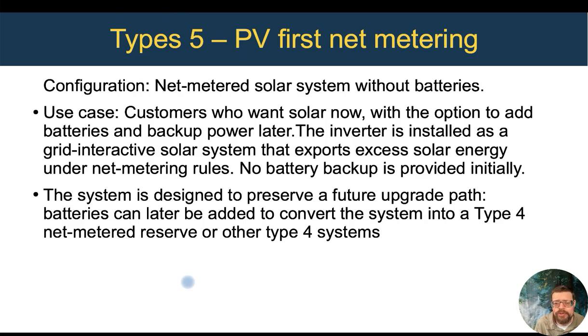lot of potential future-proofing value to your net metered grid tied system, in that when the utility says, guess what, we're now paying you 4 cents for your export instead of full net metered rate of 12 cents, you can add batteries and start doing a type 3 system. So it gives you a lot of flexibility versus putting in most of the grid tie systems that people are putting in now, where it's a little more clunky to add batteries or time of use shifting later, and adds a little more equipment. This way, all you've got to do is add the battery. If you're doing backup power, you have to add a backup power panel, and it's a bit less wiring later when something changes in the future for which type system you want.